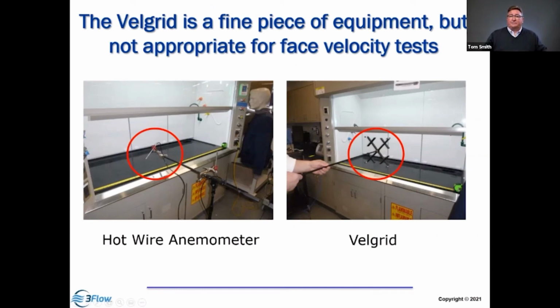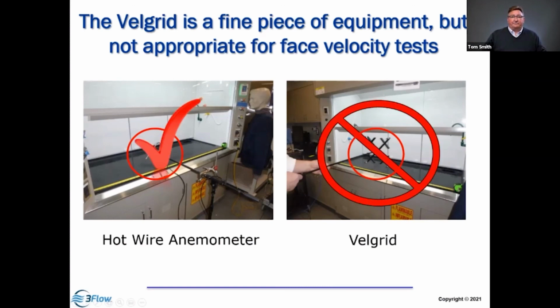A Velgrid is a perfectly good piece of equipment for measuring uniform laminar flow and velocity, like 60 feet a minute. But when you have turbulence and you have spatial and temporal variations, this instrument is just not appropriate for certification of hoods. It introduces error in your measurements. And so it is appropriate to take the hot wire, not the Velgrid. Now you can use it for spot checking, and we use it for filter measurements, we use it for lots of different tests, just not our average velocity.